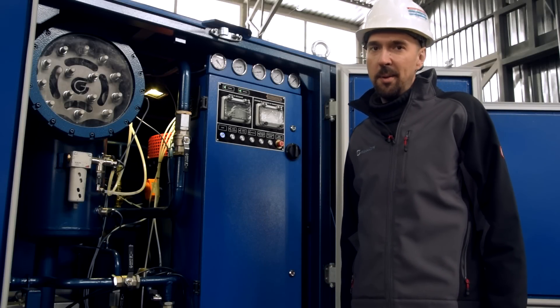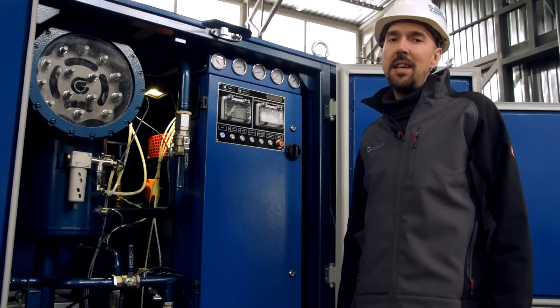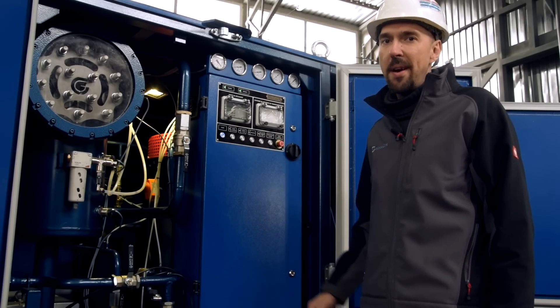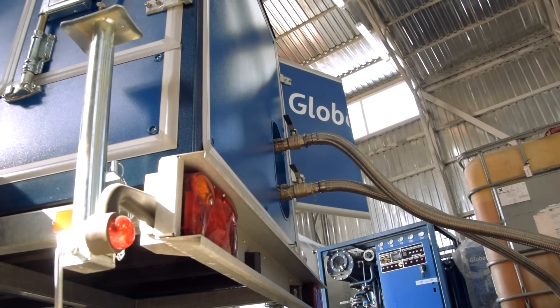This is the CMM 2.2N model, designed for purification of transformer oil by heat and vacuum, degassing of oil and removal of particulate matter. The unit can also heat electrical equipment with hot transformer oil and evacuate and dry transformers.